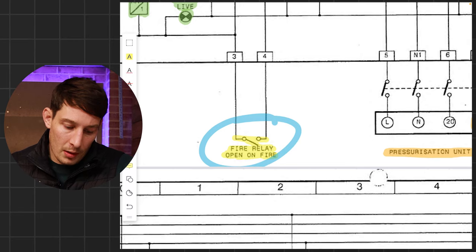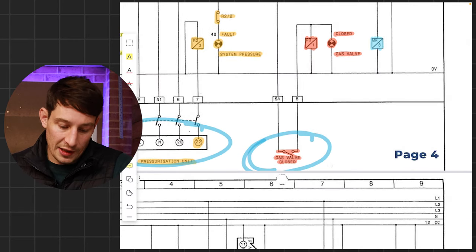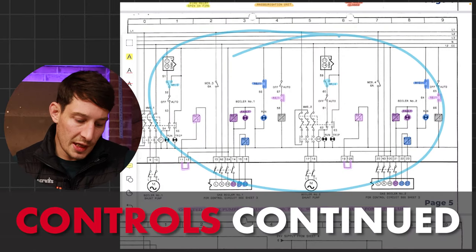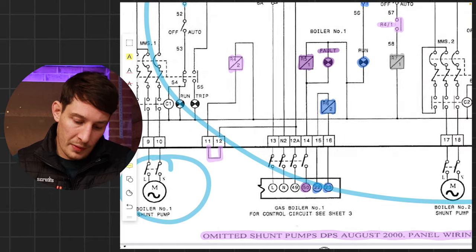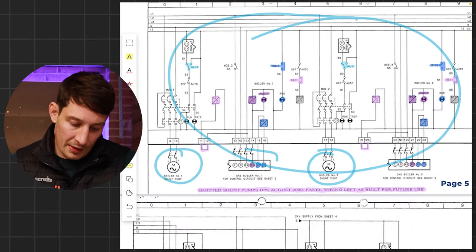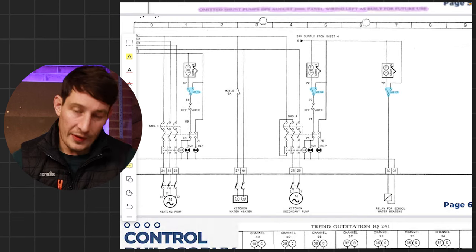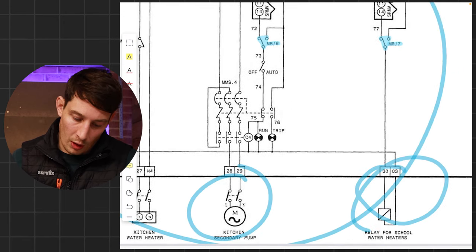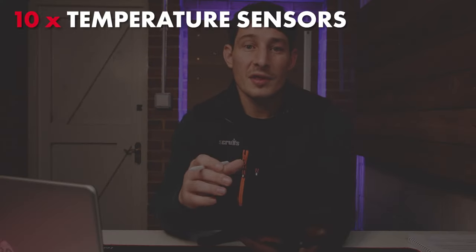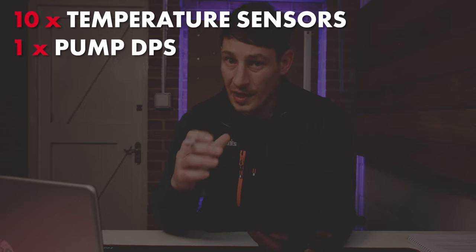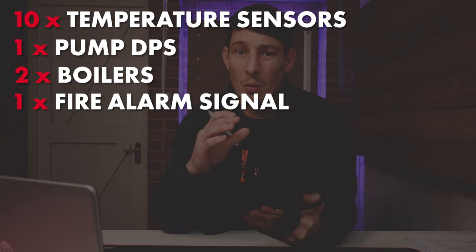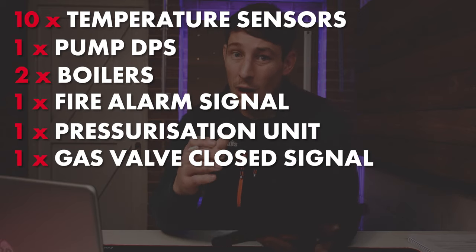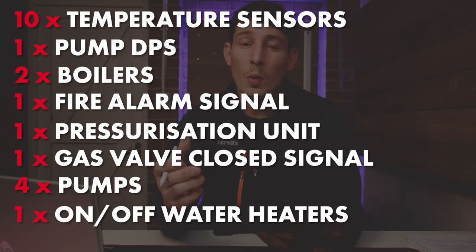We've also got a fire alarm signal, a pressurization unit, and a gas valve signal. On page six we've got some more controls — two more pumps and controls for the water heaters within the school. So as a quick recap, the devices in the field the system is currently monitoring or controlling comprise of: 10 temperature sensors, one pump differential pressure switch, two boilers, a fire alarm signal, one pressurization unit, a gas valve closed signal, four pumps, and an on/off signal for the school water heaters.